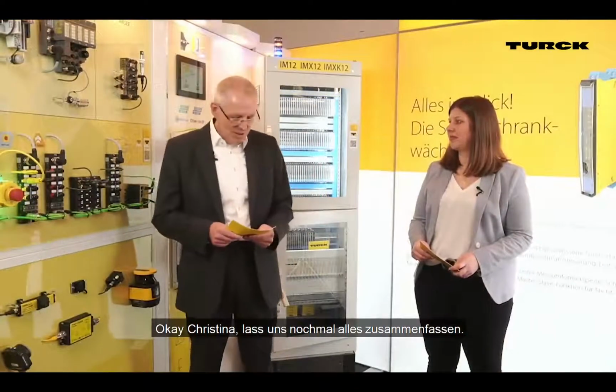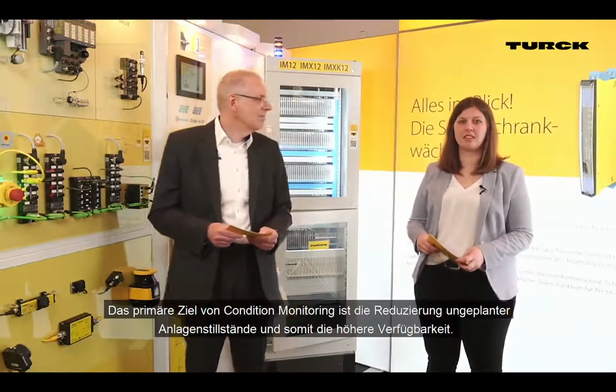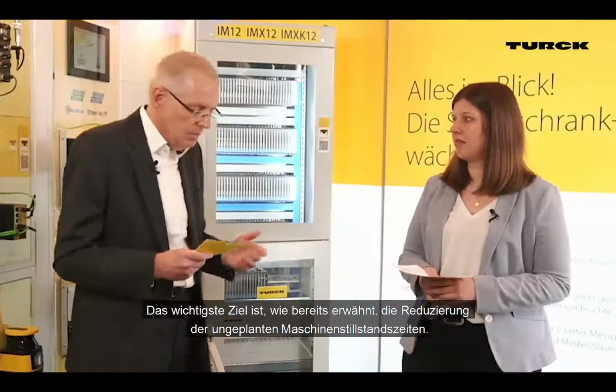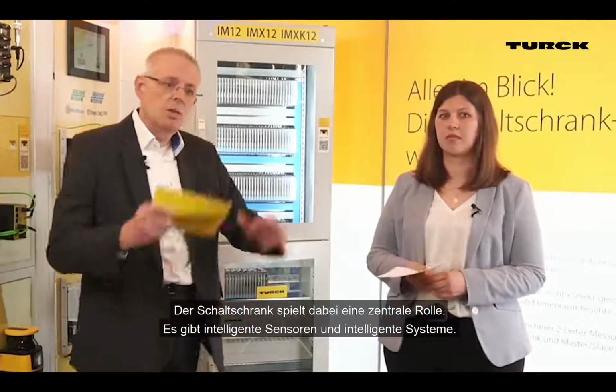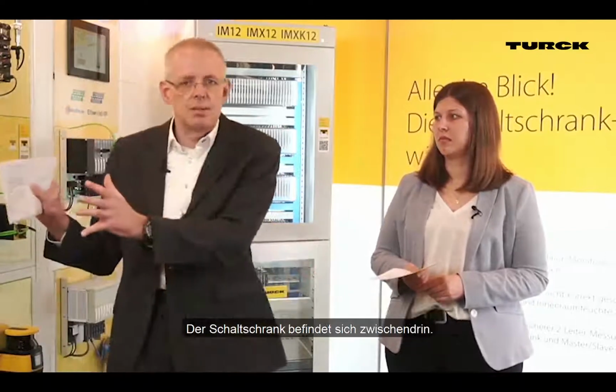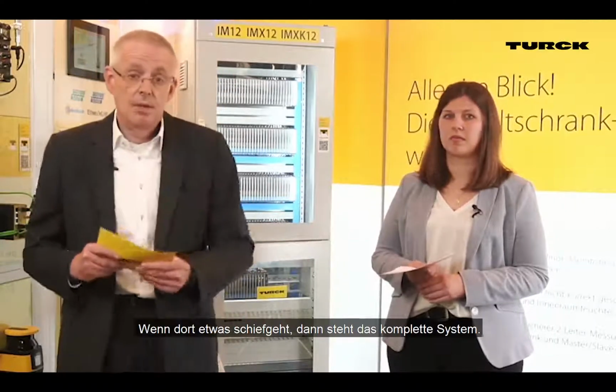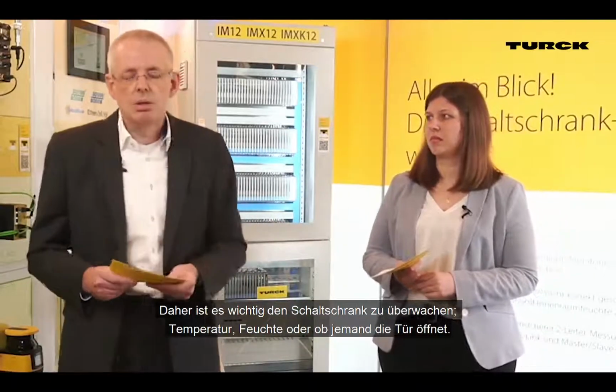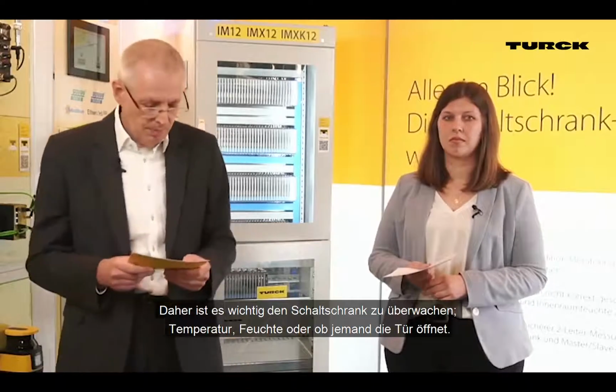Well, Christina, that's good. Let's summarize everything together. The primary goal of cabinet condition monitoring is to reduce unplanned system downtimes and thus increase availability. As we said already, the cabinet plays a central role in all of that. We have intelligent sensors, we have intelligent systems on the other end, and the cabinet is in between. If something goes wrong in the cabinet, then the complete system will fail as well. So it's really important to monitor what's going on in your cabinet, whether it's the temperature, the humidity, or if someone has opened the door.